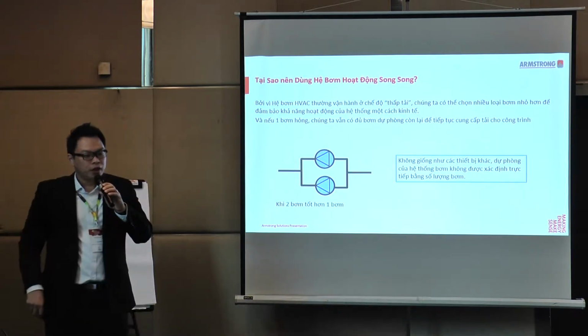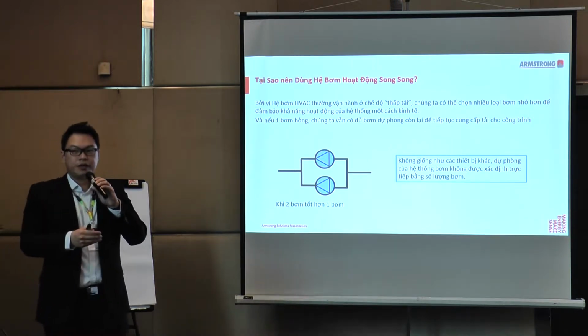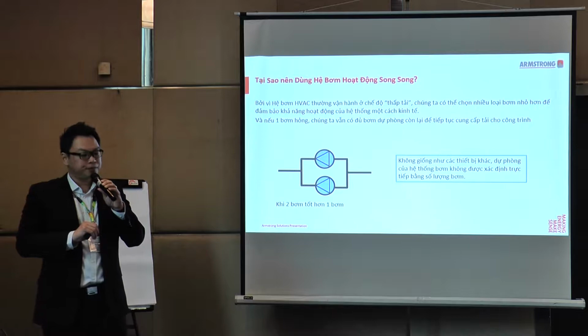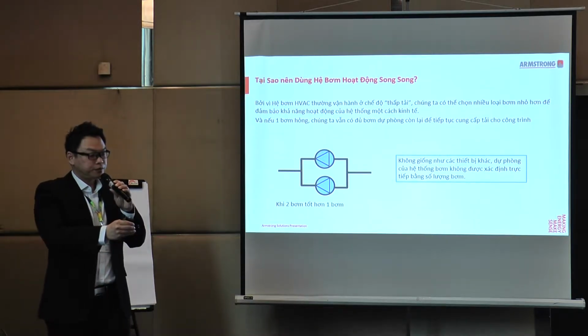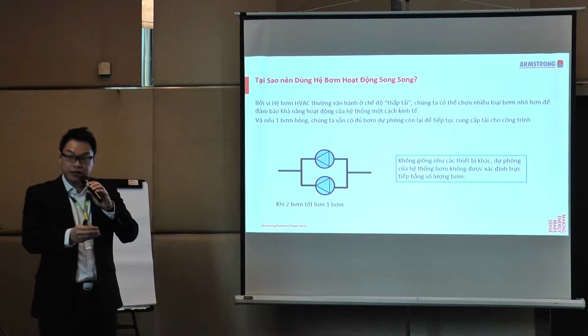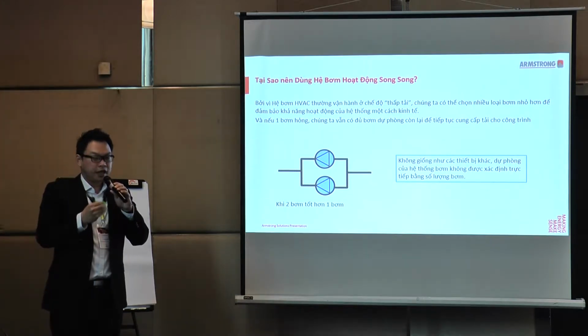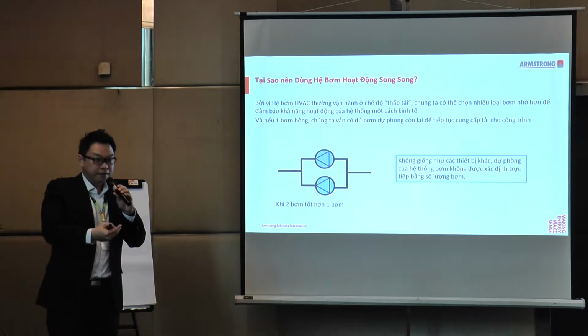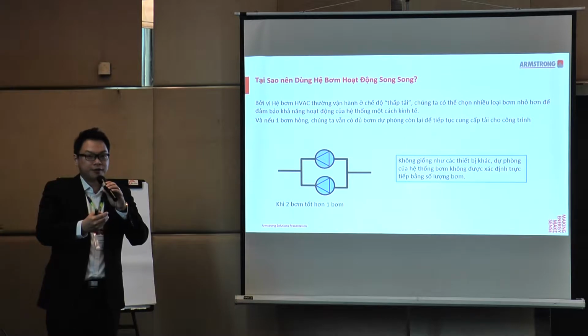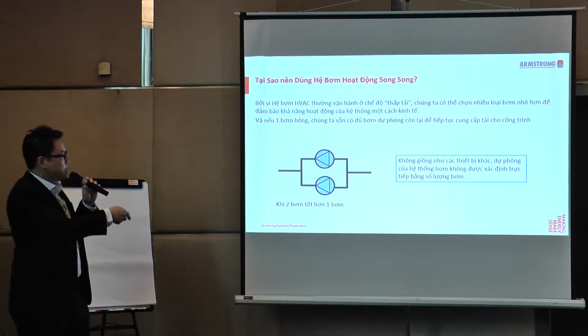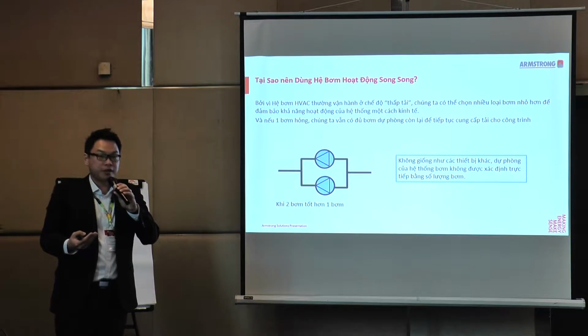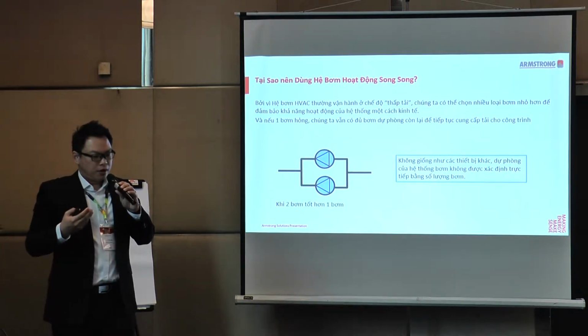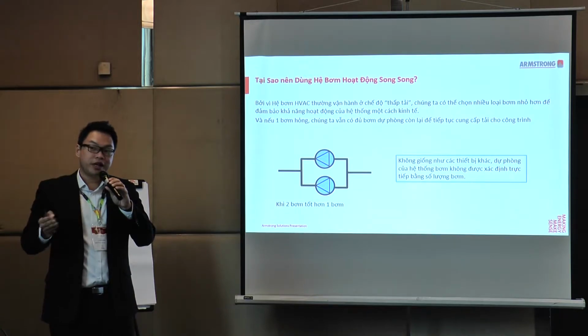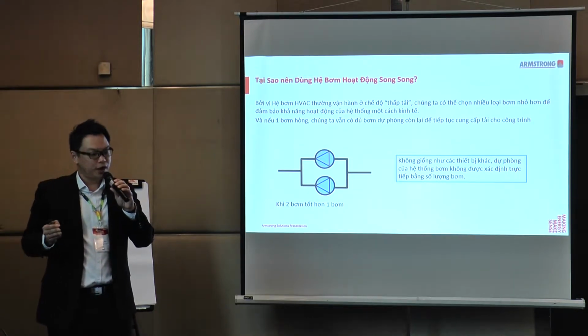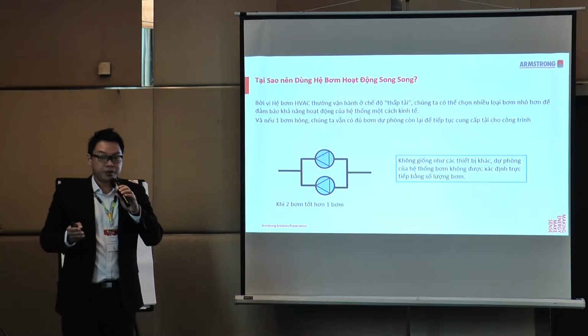Follow? So when you have two smaller pumps in operation, and if one pump fails, we'll still have sufficient redundancy or backup, and this backup will be able to handle the flow whenever a failure occurs. And over here in the box, you will see that unlike other equipment like boilers or chillers, the pump's redundancy is not a 1-to-1 ratio. It's not determined by the number of pumps.